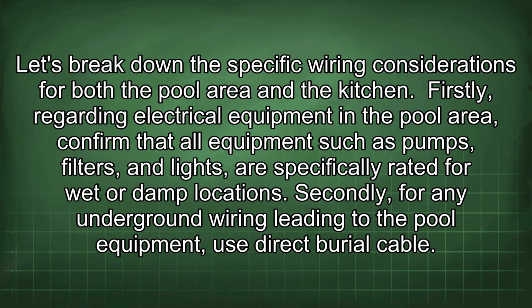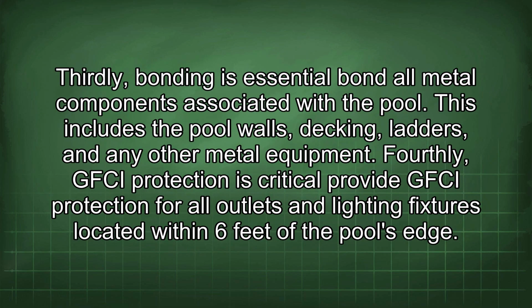Firstly, regarding electrical equipment in the pool area, confirm that all equipment such as pumps, filters, and lights are specifically rated for wet or damp locations. Secondly, for any underground wiring leading to the pool equipment, use direct burial cable. Thirdly, bonding is essential. Bond all metal components associated with the pool. This includes the pool walls, decking, ladders, and any other metal equipment. Fourthly, GFCI protection is critical. Provide GFCI protection for all outlets and lighting fixtures located within 6 feet of the pool's edge.